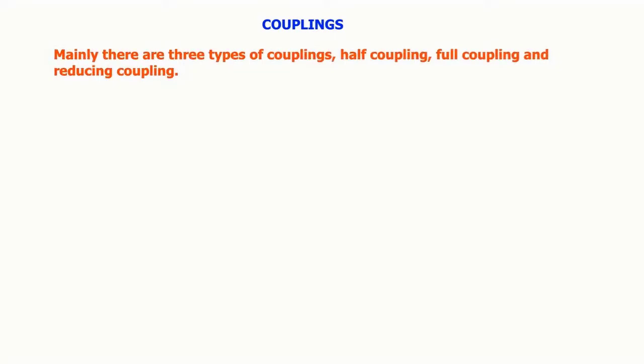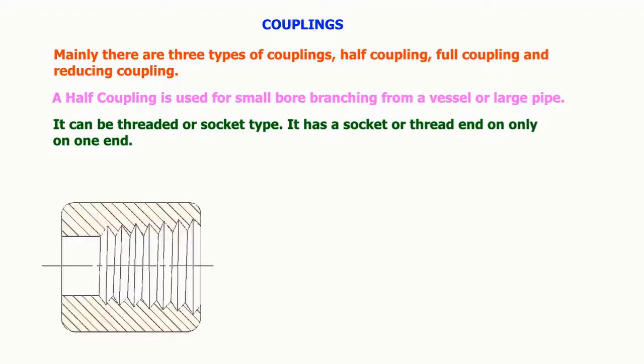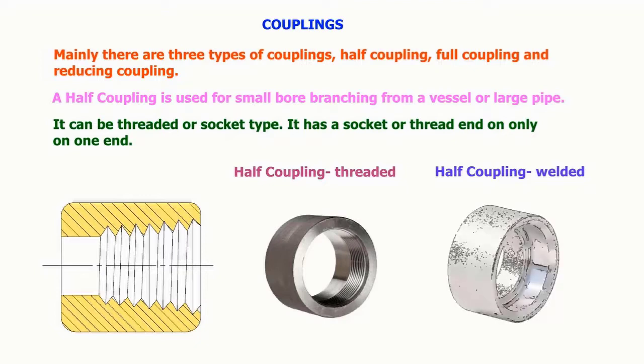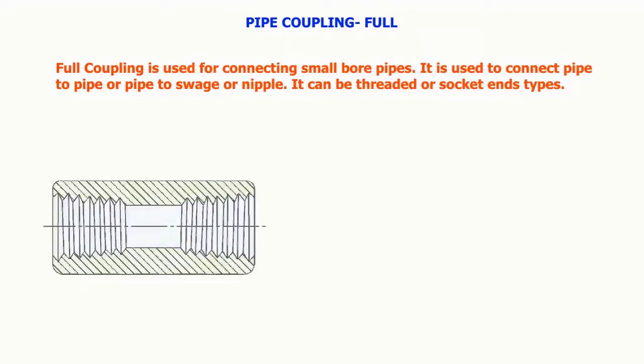Mainly there are three types of couplings: half coupling, full coupling, and reducing coupling. A half coupling is used for small bore branching from a vessel or large pipe. It can be threaded or socket type. Full coupling is used for connecting small bore pipes, to connect pipe to pipe or pipe to swage or nipple. It can be threaded or socket end types.